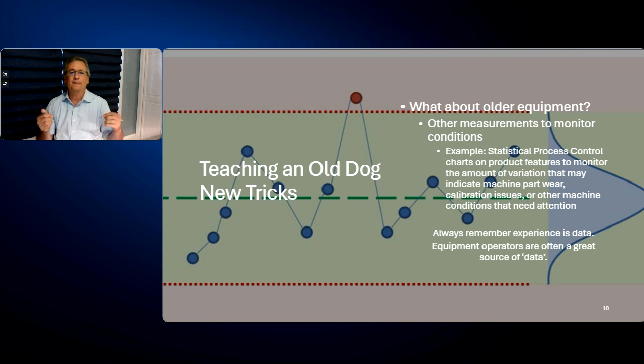What was great is that she and her technicians understood the conditions they had to monitor, informally. They would know, okay, this machine's starting to get a little out of whack, we better start calling in the technicians, the service providers. They were outside service providers, usually the OEM they bought the equipment from would offer the service. Now, to put this in context, they would run the equipment until failure. That's still very, very typical today.